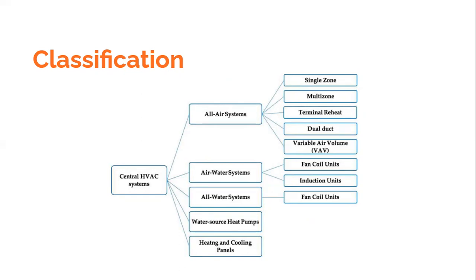At times you would find that there are also chilled water pipes which are laid along with the ducting system. So in those systems you would have a mix of air as a fluid for transferring the cooling effect or heating effect, as well as water as a fluid which would transfer the cooling effect or heating effect. So you might find that there is a fan coil unit and an induction unit, which is basically where you would have an exchange of heat between the air and the water. For example, if there is a fan coil unit meant for summer air conditioning, in the fan coil unit you would find that there are chilled water pipes which are flowing, and there is air which is flowing. There is exchange of heat between the air and water, and this is how you get the cooling and dehumidification process happening. So in air water systems, you would find both the fluids, that is air as well as water, being used.